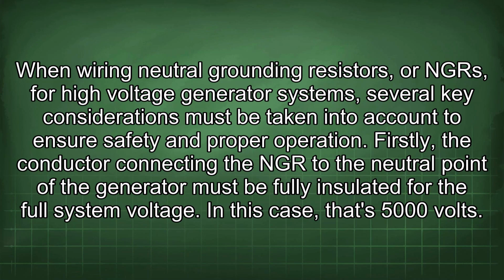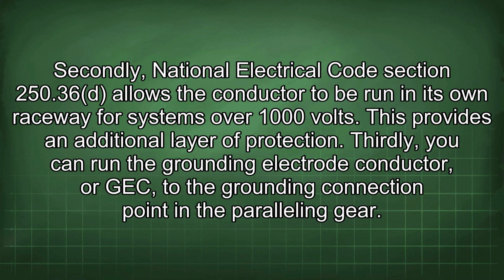When wiring neutral grounding resistors, or NGRs, for high-voltage generator systems, several key considerations must be taken into account to ensure safety and proper operation. Firstly, the conductor connecting the NGR to the neutral point of the generator must be fully insulated for the full system voltage. In this case, that's 5000 volts. Secondly, National Electrical Code Section 250.36 allows the conductor to be run in its own raceway for systems over 1000 volts. This provides an additional layer of protection.